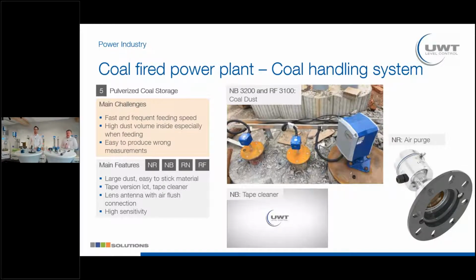So with high dust content, the tape cleaner just cleans the tape, so we get no false signals or pollution inside the mechanical housing. This is the effect of the tape cleaner. We can also have a redundant system, combining a continuous level transmitter with a level limit switch. This is what we did in this coal dust silo. We installed the NivoBob, and in addition the level switch, the RF Nivo, as a full alarm, and the NivoBob for continuous measurement.